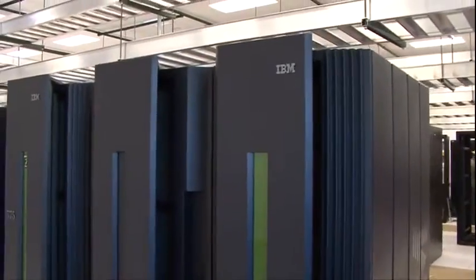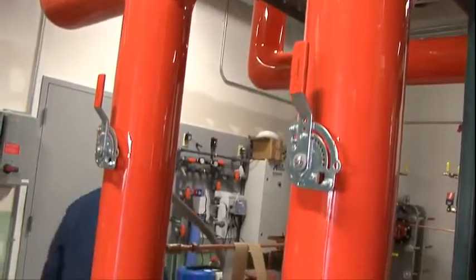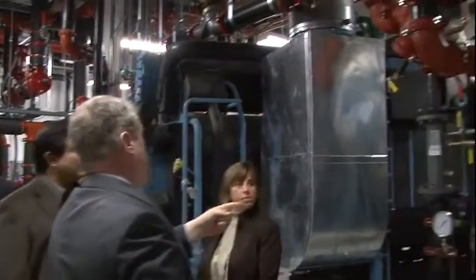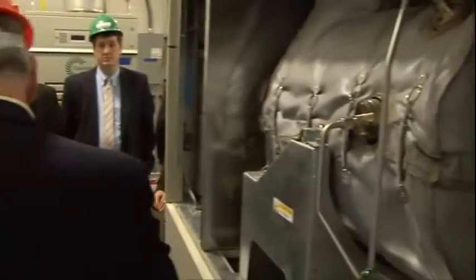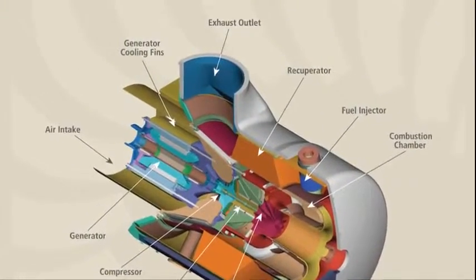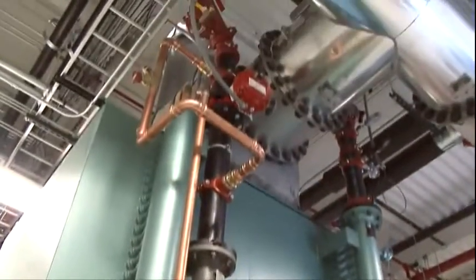One of the design's most efficient features is trigeneration. That's electricity, heating, and cooling, all from a single burn of natural gas. We're using an on-site combined cooling and power system. It's based on microturbines driving high-speed electric generators, and the waste heat from that turbine is used for generating the necessary cooling for the data center and for an adjacent building.